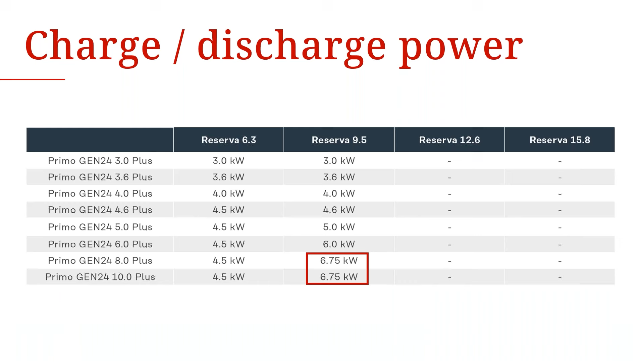Let's have a look about the maximum what's possible in terms of storage capacity with the Reserva connected to a Primo Gen24, Simo Gen24, or Verto Plus. So max three phase on a Simo Gen24 Plus will be 63.2 kilowatt hours. So that's 4 stacks. The maximum capacity on a single phase inverter, so on our Primo Gen24 Plus range, will be 38 kilowatt hours. And for the Verto Plus, it will be also 63.2 kilowatt hours. So 4 towers with maximum sizing. So the parallel stacks must be the same size. So that means if one stack has, for example, 3 battery modules, if you add a second one, it also needs to have 3 battery modules.